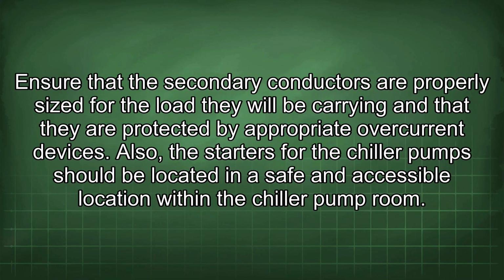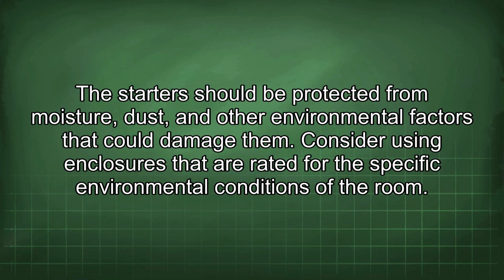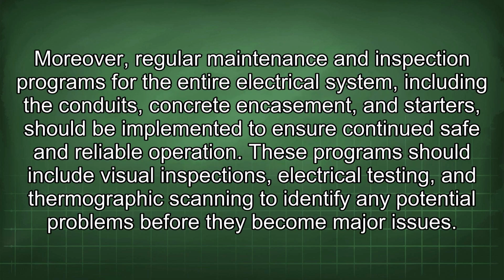Ensure that the secondary conductors are properly sized for the load they will be carrying and that they are protected by appropriate overcurrent devices. Also, the starters for the chiller pump should be located in a safe and accessible location within the chiller pump room. The starters should be protected from moisture, dust, and other environmental factors that could damage them. Consider using enclosures that are rated for the specific environmental conditions of the room. Moreover, regular maintenance and inspection programs for the entire electrical system, including the conduits, concrete encasement, and starters, should be implemented to ensure continued safe and reliable operation.